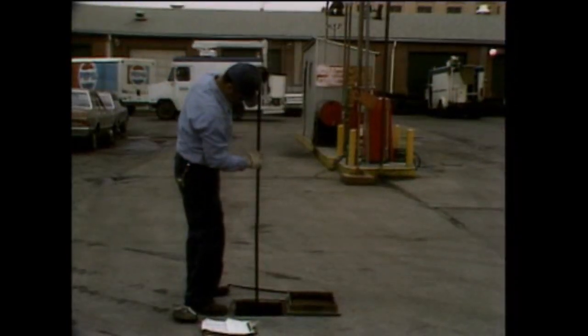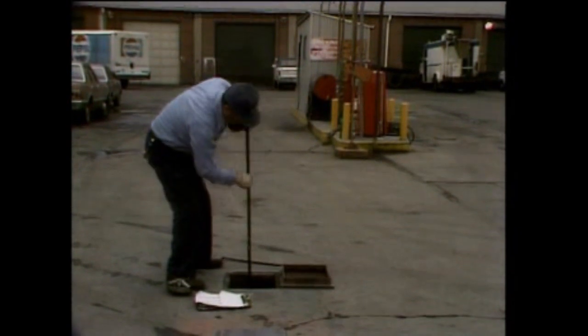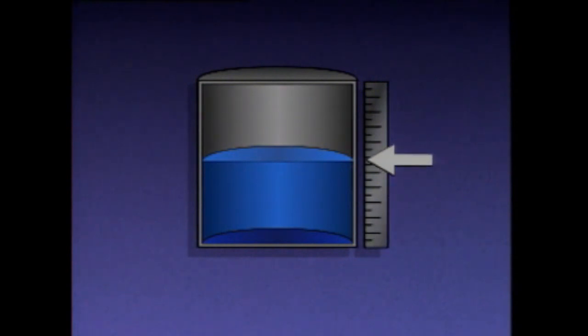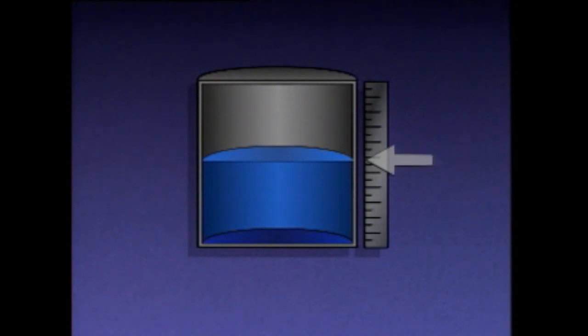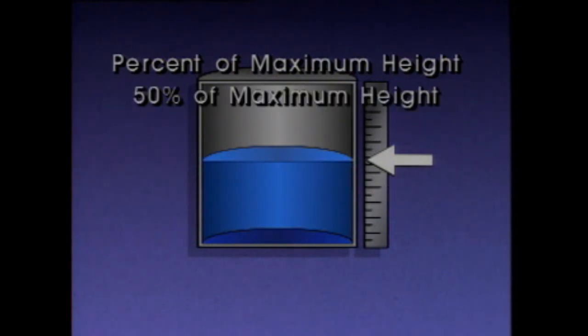The last process variable we'll discuss is level. Level can be defined as the position of a surface above or below a fixed reference point. For instance, in this illustration, if the reference point is at the bottom of the tank, measurements are taken from the bottom to the surface, indicating how much of the tank is filled. If the reference point is at the top of the tank, measurements are taken from the top to the surface, indicating how much of the tank remains to be filled. Another way the level in this tank can be expressed is as a percent of maximum height — for example, the level in this tank is at the halfway mark, so we can say that the level is 50% of maximum height.